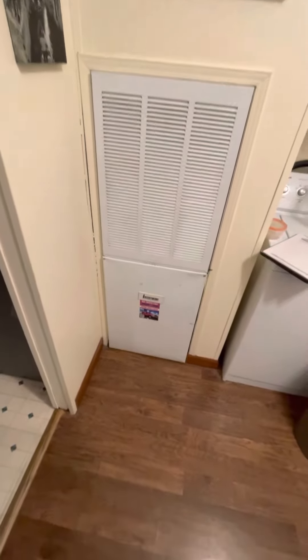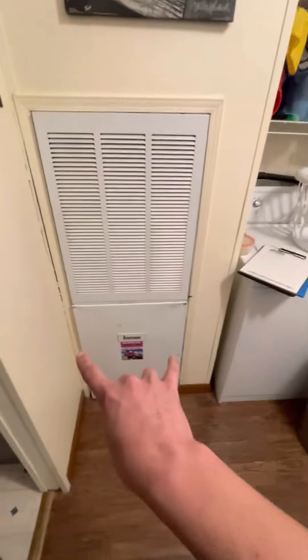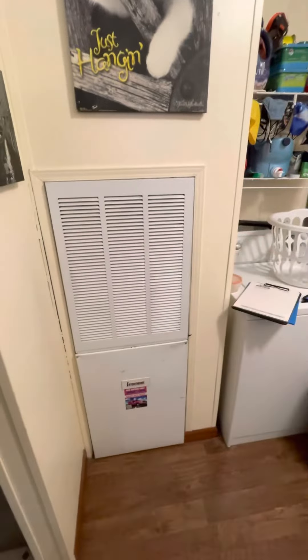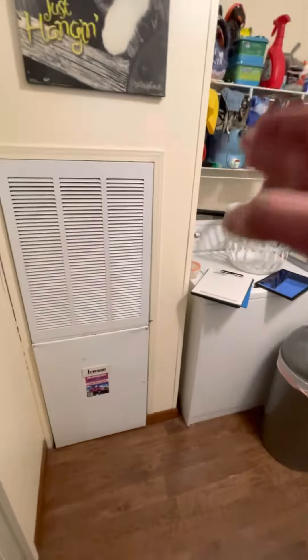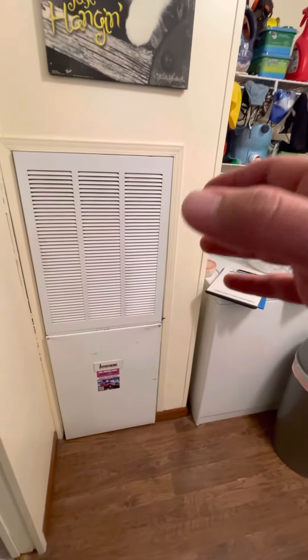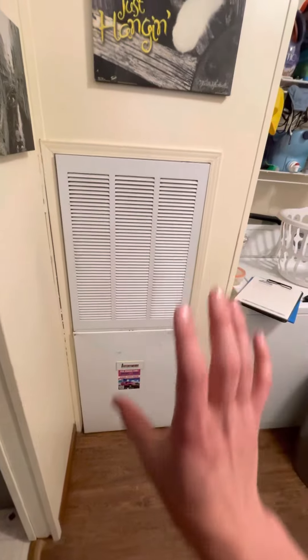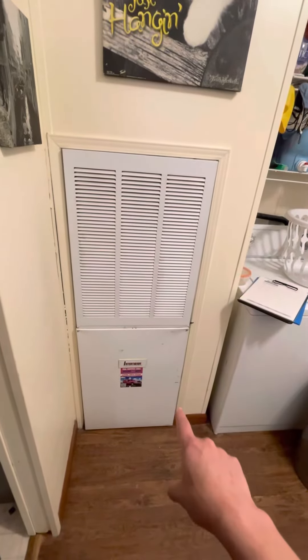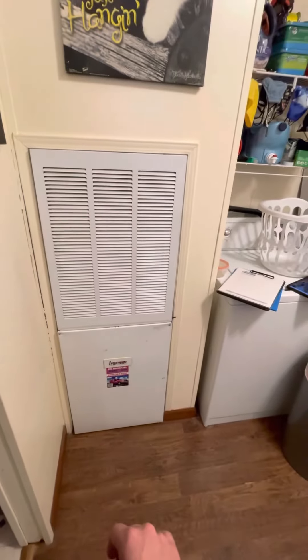This is the existing electric manufactured house furnace that we have right now. We have a 20 width by 56 top to bottom with some really nice trim on the side. Please make sure to be careful with that trim so we can put it all back together. The coil and everything is right up here on the main coil — there's the return for this system — and then you have the existing electric heat kit and system down below on this Intertherm.